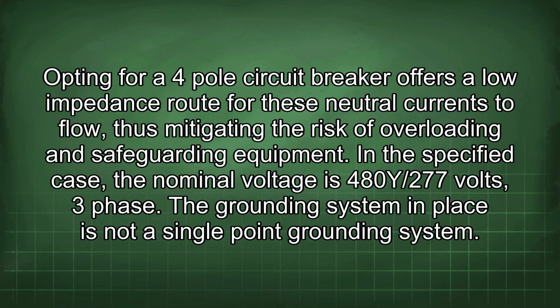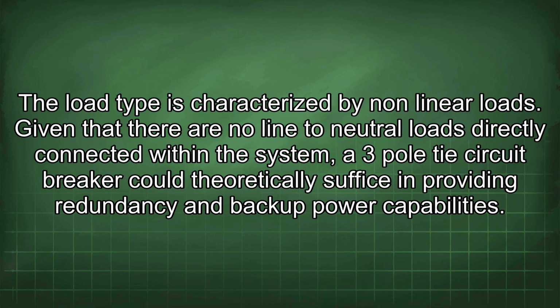In the specified case, the nominal voltage is 480Y/277 volts, 3-phase. The grounding system in place is not a single-point grounding system. The load type is characterized by nonlinear loads. Given that there are no line-to-neutral loads directly connected within the system, a 3-pole tie circuit breaker could theoretically suffice in providing redundancy and backup power capabilities.